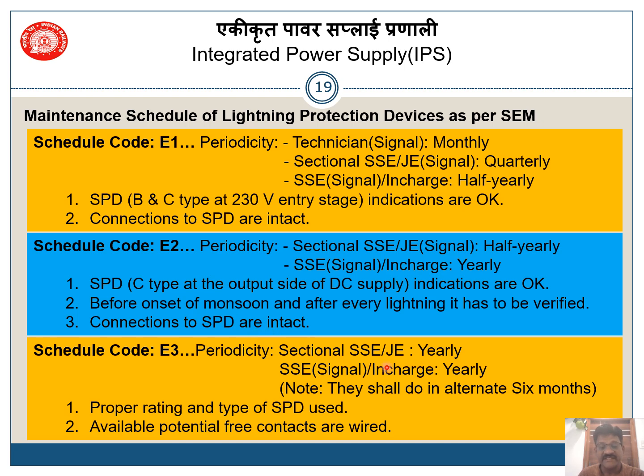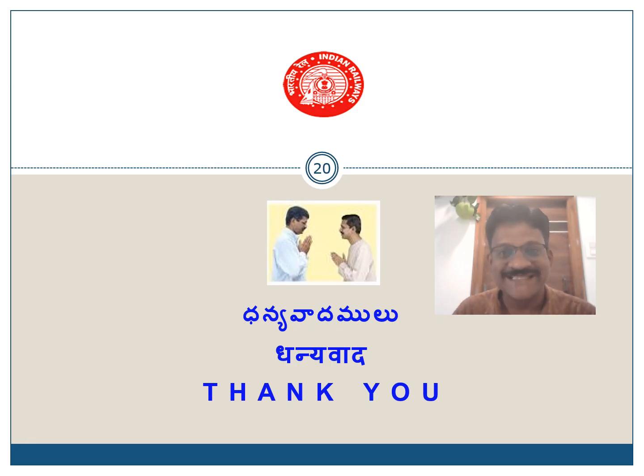While once in a year the following things shall be done. Proper rating and type of SPD is used. If not, it shall be replaced. Potential free contacts which are wired shall also be checked for validation through data logger. Thank you.